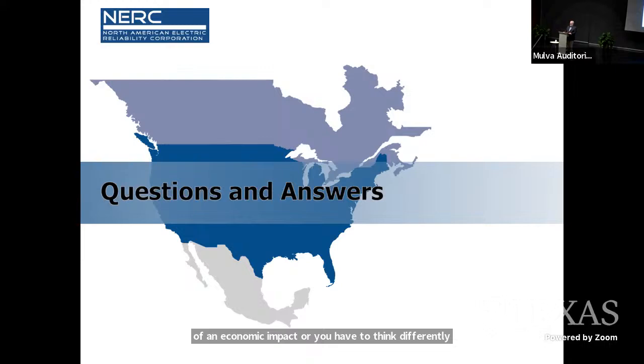We have to think differently about both. The problem with the methods we used to use in the past is that they used to mask out some of the long duration events. The whole idea with a 1-in-10 standard was that it was one event in 10 years, and there were some basic assumptions. One was that every day was independent of the other—meaning if you had a problem, the next day it's gone, the plants are back up and running within a day. That was one major assumption. The other was a copper sheet assumption, meaning there was no transmission worries, no congestion. The third is that it's based on random failures of large plants, with probabilities stacked on top of each other—so 0.9 times 0.9 times 0.9, if your forced outage rate is 0.1, you multiply 0.1 times 0.1.